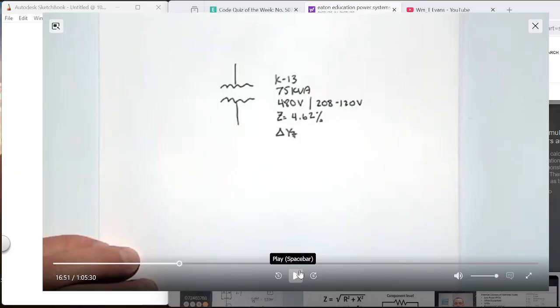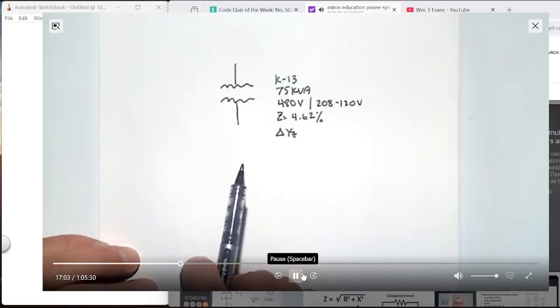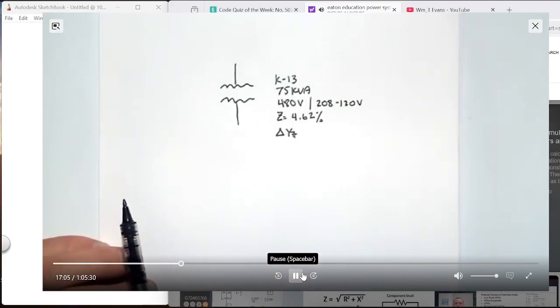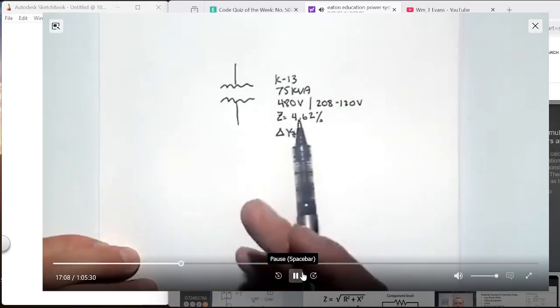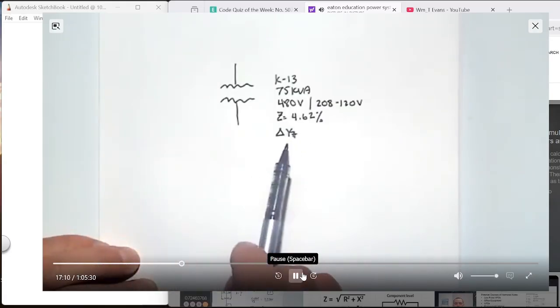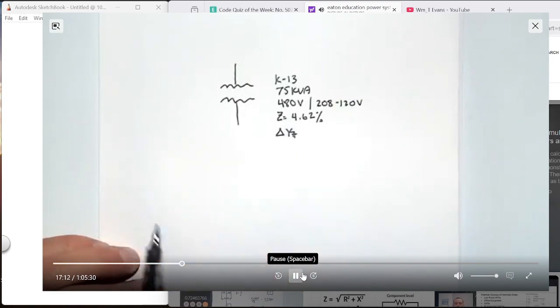By the time you get done with it, you'll be experts at calculating fault current. You'll have 10 examples, different ones of different types. Transformer names like K13, TP1, HMT, all kinds of strange names might come up. That's not going to affect your calculations for these things. It actually does affect the impedance of the transformer when it's put together, but whatever's on the nameplate is what you need. This information on the nameplate is all you need.